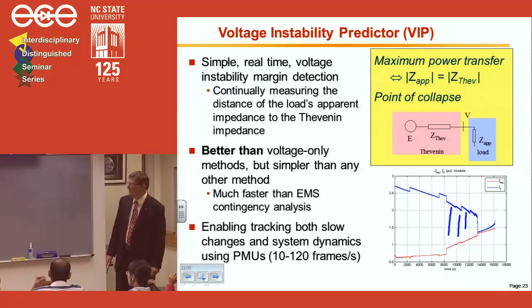Originally the idea was to use voltage as an indicator, but I'll show you why voltage is not such a great indicator. Instead you track your Z Thevenin and test your Z load, actually measuring the margin. As you go along, you can know exactly how close you are to the voltage instability point, and then detect it and take control actions as needed. This is much faster than doing it through EMS SCADA systems—you use PMUs for this, so it's more accurate.